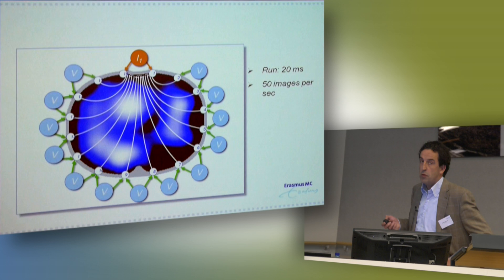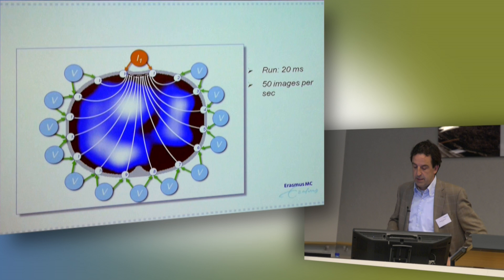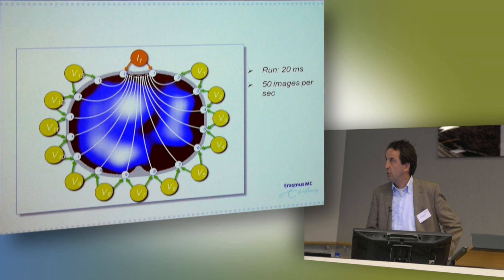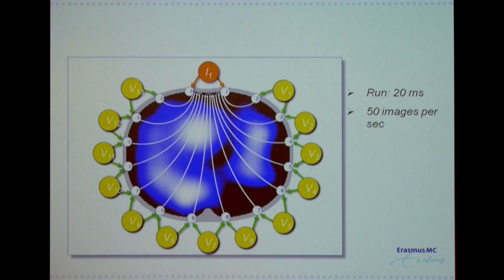Between a pair of electrodes a small current is injected, and you are measuring the time needed to reach the other electrodes. In one second you are collecting 50 digital images. Here in white is a large impedance change, and the impedance change in the thorax is due to ventilation — air coming in. Blue is smaller impedance change, and black is no impedance change. Like the CT scan, this is the right lung, and here in this example this is the left lung.